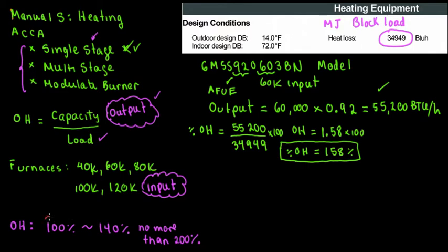158% is not within what Manual S recommends, because Manual S recommends from 100 to 140, no more than 200. What would be the other option? This is a 60K furnace. What if we go for a lower value? A lower value would be option two. Let's put the other model: GMSS920402BN. These furnaces are discontinued, by the way.